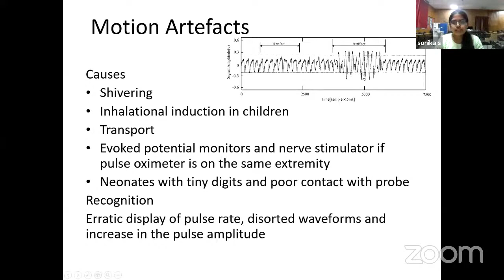Motion at the sensor site can cause artifact that the pulse oximeter is unable to differentiate from the arterial pulsation. The causes for motion artifacts are shivering, inhalation induction in children, transportation, evoked potential monitors and nerve stimulators if the pulse oximeter is on the same extremity, and neonates with tiny digits and poor contact with the probe. How are we going to recognize these motion artifacts? There is an erratic display of the pulse rate, distorted waveform, and also an increase in the pulse amplitude. In this diagram, we can see the motion artifact where there are distorted waveforms and also an increase in the pulse amplitude.